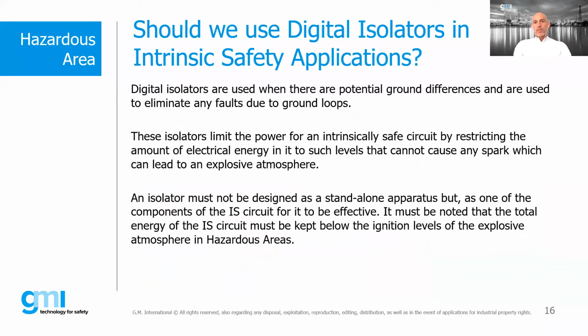So should we use the digital isolator in intrinsically safe applications? The thing is, the isolator limits the power for the intrinsically safe circuit by restricting the amount of electrical energy to low limits, so it won't cause any spark. In this case, if you want to use this kind of digital isolator, the isolator must not be designed as a standalone apparatus, but is one of the components of the IS circuit. So just an isolator is not sufficient for avoiding any sparking situation in an explosive atmosphere.